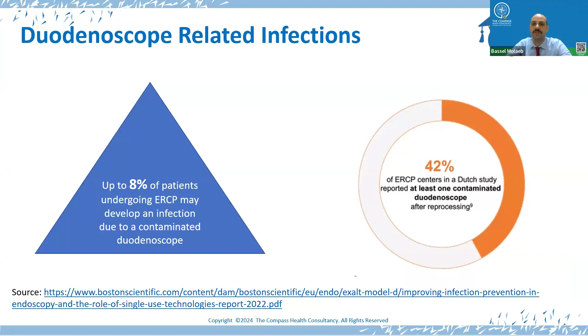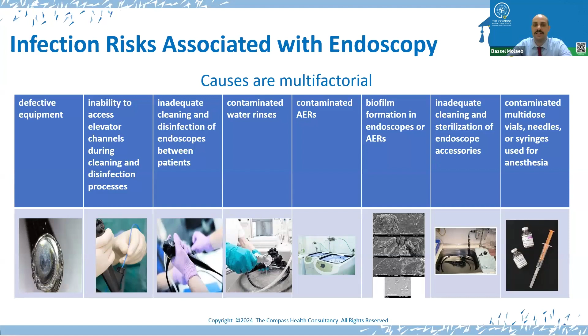Talking deeper about the causes of these failures in scope reprocessing, as Jill addressed in the challenges, those causes are multifactorial and could include defective equipment, as we saw in the borescope image, inability to access the elevator channels during cleaning and disinfection processes, especially for the duodenoscope, inadequate cleaning and disinfection of endoscopes between patients, contaminated water rinses, contaminated automatic endoscope reprocessors or AERs, biofilm generation, inadequate cleaning, disinfection and sterilization of endoscope accessories, in addition to contaminated multi-dose vials, needles, syringes, or other items used during anesthesia or patient care.